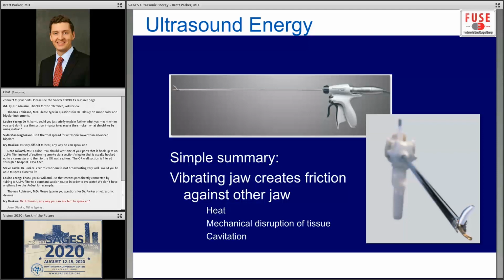So I was just mentioning the ways that ultrasonic energy devices are used in the operating room. The final phenomenon is cavitation, and this is somewhat difficult to comprehend, but in general, it's a phenomenon that occurs in less dense tissue, such as fat, and leads to cellular vaporization, which expands the tissue that surrounds the jaws of the device, and the gaseous product forms these microbubbles or cavities that facilitate dissection and enhance the surgeon's visibility without smoke.